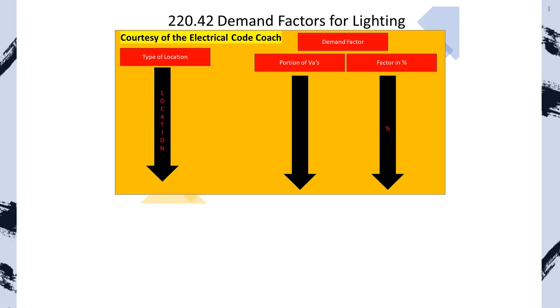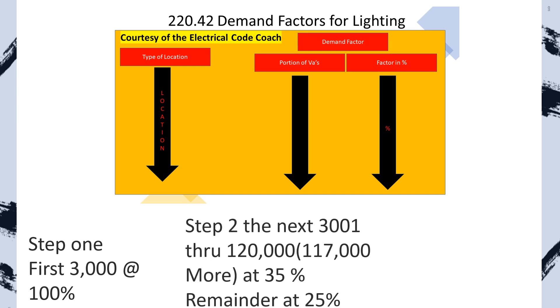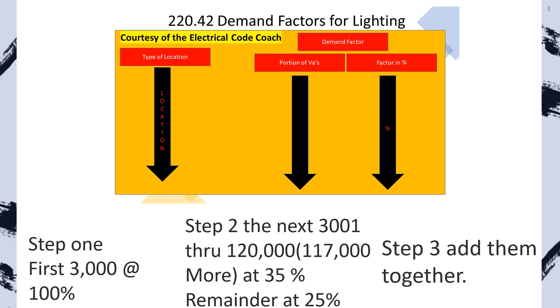When looking at this table, we're going to see a multi-layered demand factor for dwelling units. Step one, we're going to take the first 3,000 VAs at 100%. Step two, we're going to take in between 3,001 through 120,000 — which is technically just another 117,000 more — at 35%. And then we're going to take anything above and beyond that at 25%. Then step three, we add them back together: we take the original 3,000 that we set to the side, then we take that new reduced load, add those two together, and that gives us our total load.